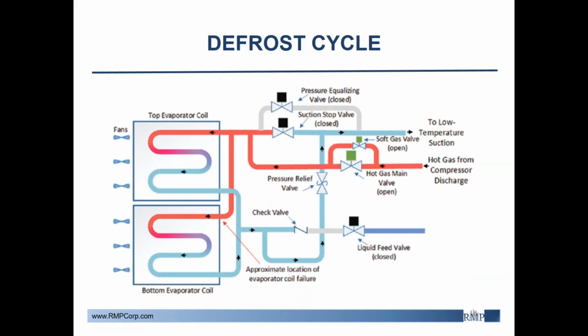So here's a schematic that displays the configuration of the defrost system. Refrigeration involves sending the cold liquid feed through the coils via the liquid feed valve. During defrost mode, this valve, along with the suction stop valve, are closed, and hot gas is pumped through the system. In the case of this incident, the hot gas was never depressurized and remained in the coils upon startup. The liquid feed valve and suction stop valve were opened. Low temperature liquid was fed back into the system and condensation-induced shock occurred.